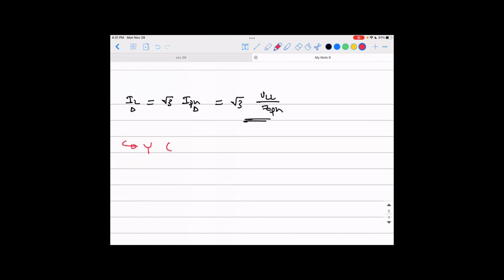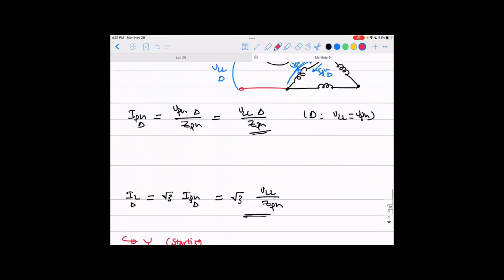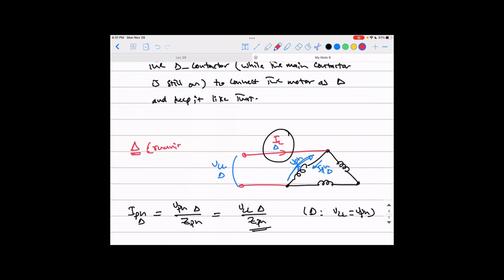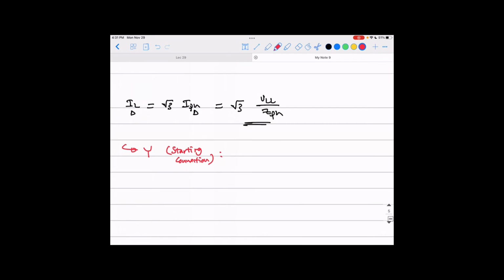What about the Y connection, which is the starting connection? The delta connection, I'm going to call it the running connection. That is the connection the motor will keep running with, but the Y is just the starting connection. If the motor is started with the Y connection, the phases will look like that. You have 3 phases like that and connected like that. Again, that is your line connections, and that's what we're more concerned about. That is our I line. I'm going to call it I line Y, and that is V line to line, which for the delta is actually still the same line to line. That is V phase here, the voltage over the phase for the Y connection, and that is the current going inside the phase for the Y connection.